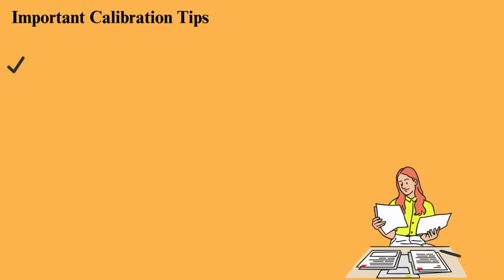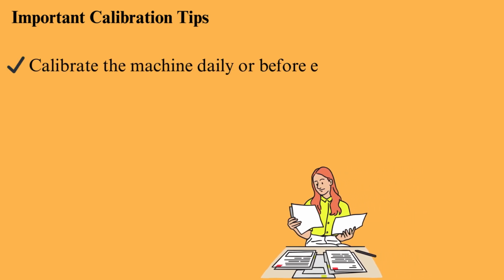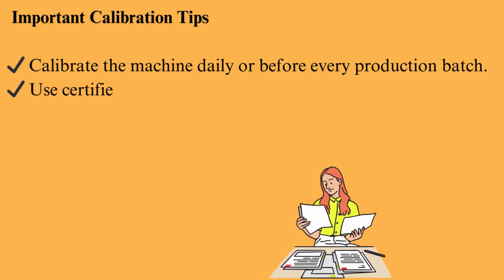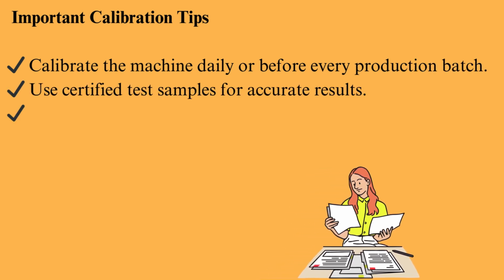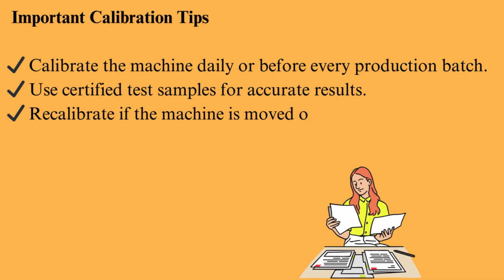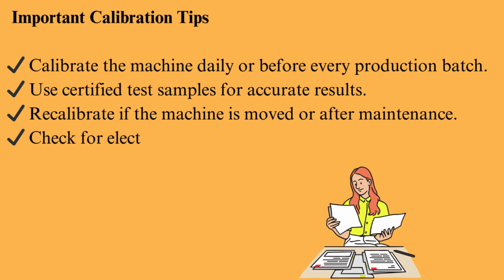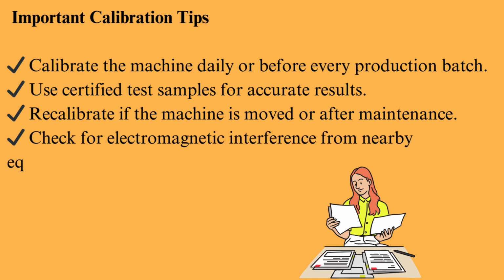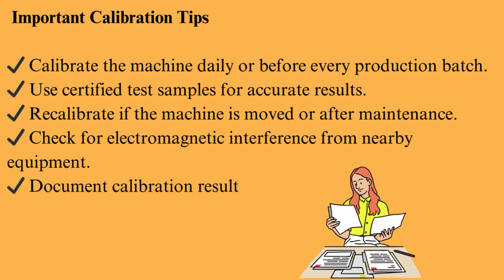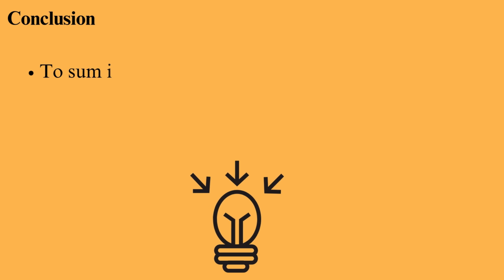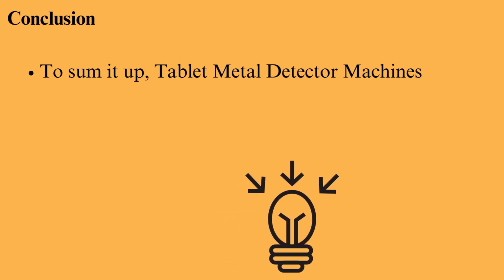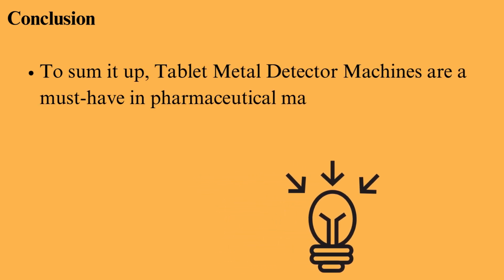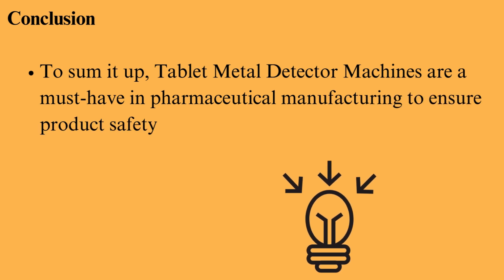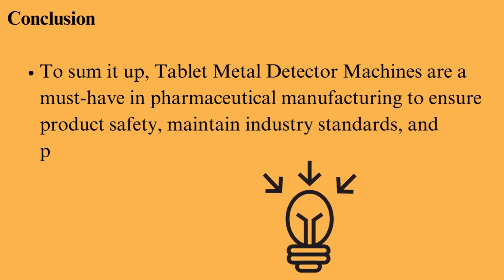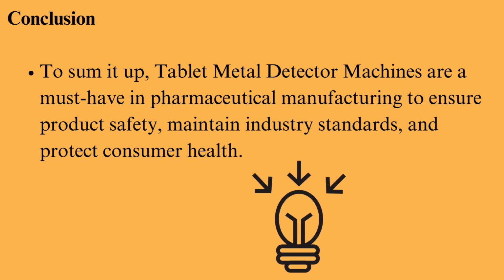Important calibration tips: calibrate the machine daily or before every production batch; use certified test samples for accurate results; recalibrate if the machine is moved or after maintenance; check for electromagnetic interference from nearby equipment; and document calibration results for regulatory compliance. Conclusion: to sum it up, tablet metal detector machines are a must-have in pharmaceutical manufacturing to ensure product safety, maintain industry standards, and protect consumer health.